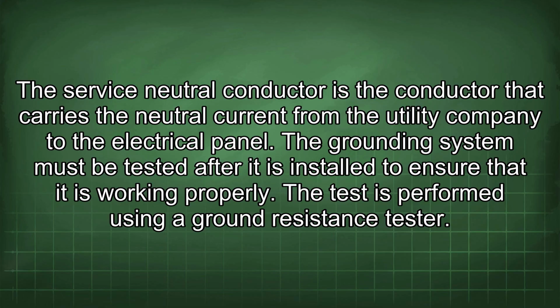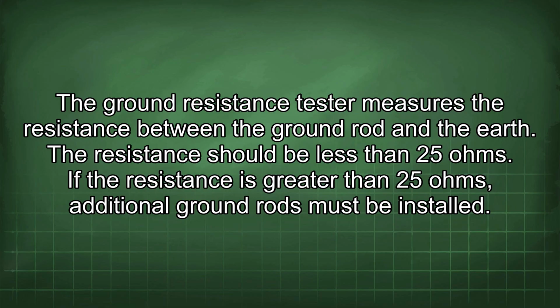The grounding system must be tested after it is installed to ensure that it is working properly. The test is performed using a ground resistance tester. The ground resistance tester measures the resistance between the ground rod and the earth. The resistance should be less than 25 ohms. If the resistance is greater than 25 ohms, additional ground rods must be installed.